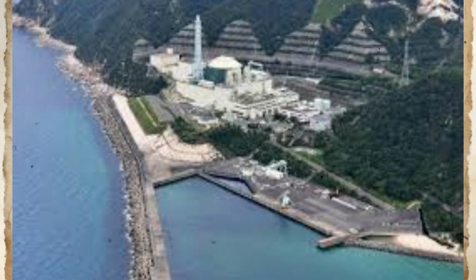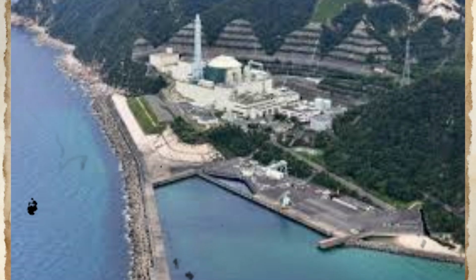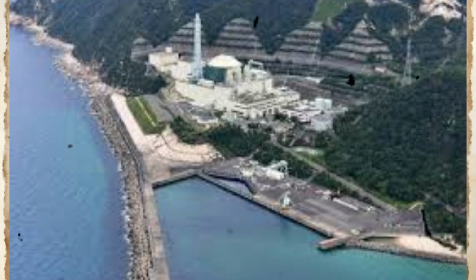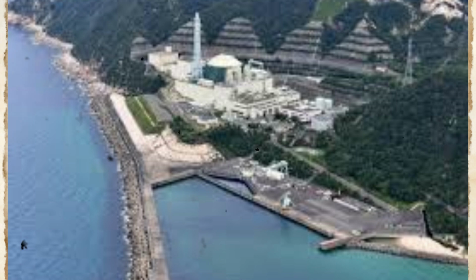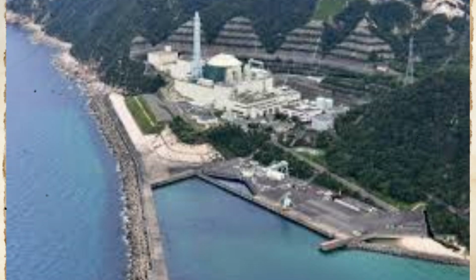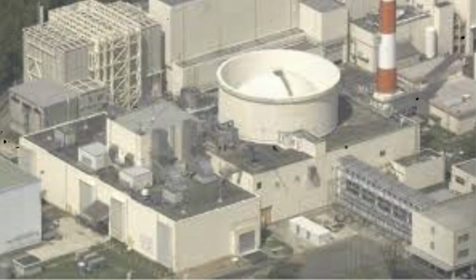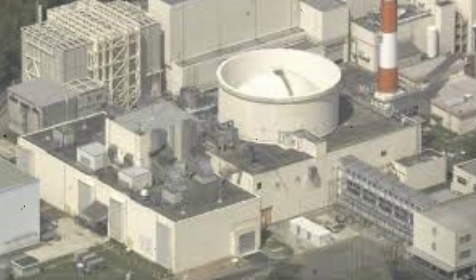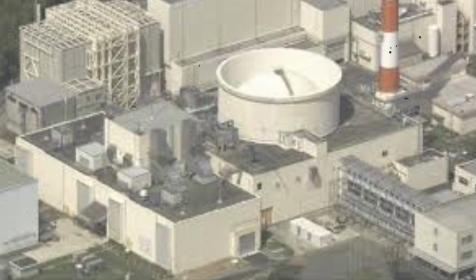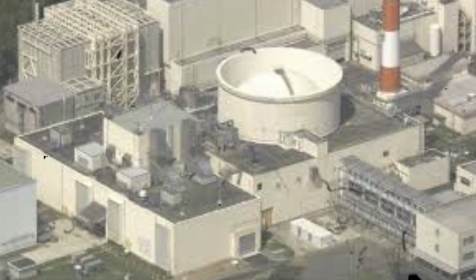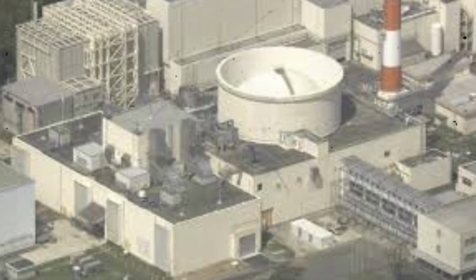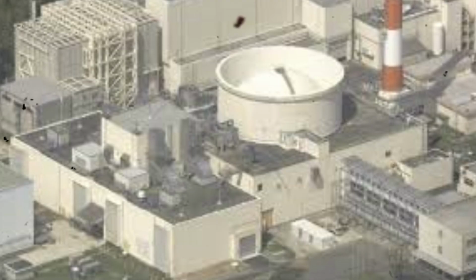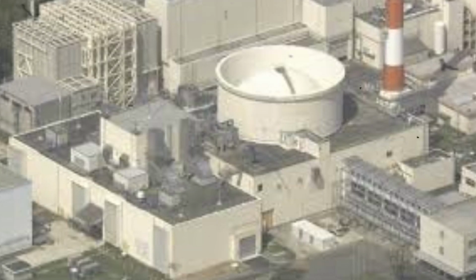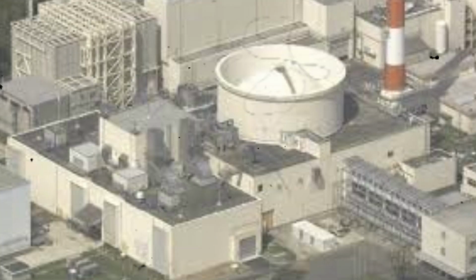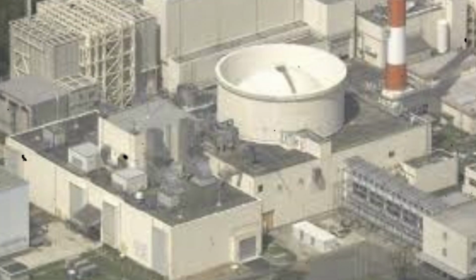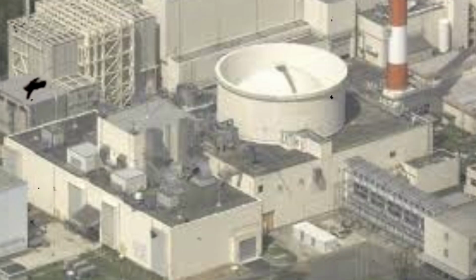This measurement imperative created an immediate engineering conflict. Liquid sodium, while an excellent heat transfer medium, proves extraordinarily hostile to instrumentation. At operating temperatures exceeding 500 degrees Celsius, direct contact between sodium and most sensor materials results in rapid corrosion. The solution adopted at Monju, consistent with fast reactor practice worldwide, involved housing temperature sensors within protective wells that extended into the sodium flow stream while isolating the sensing elements from direct sodium contact.